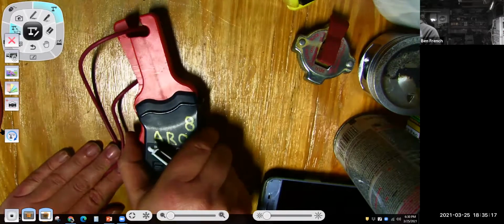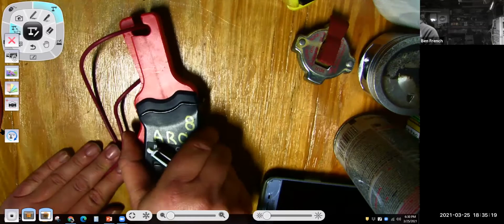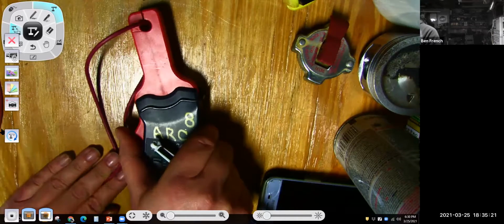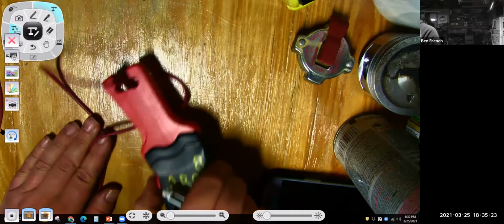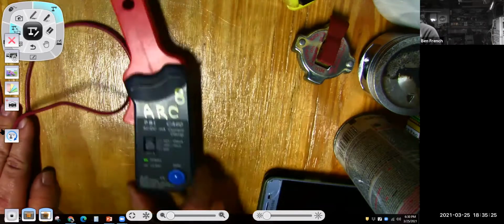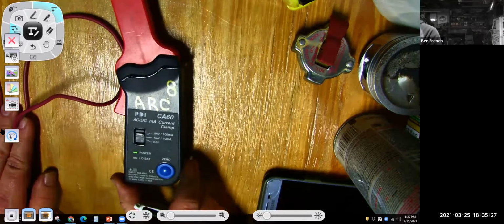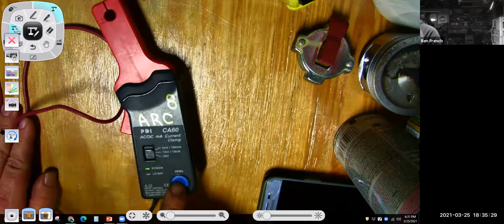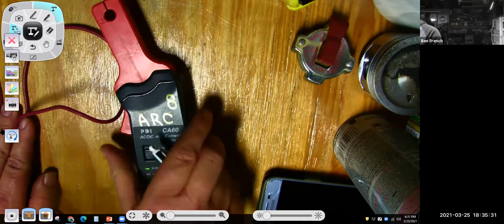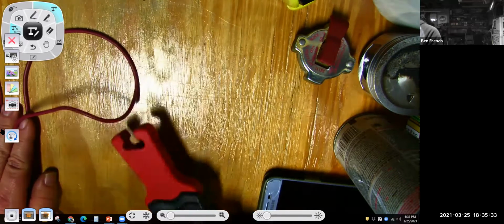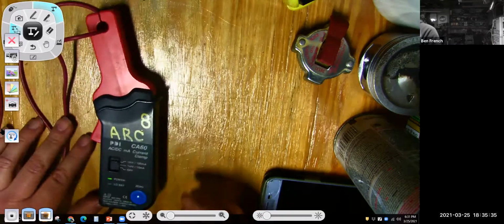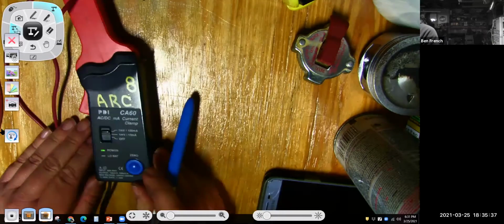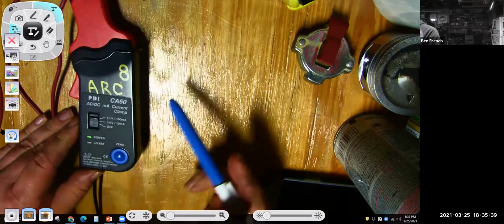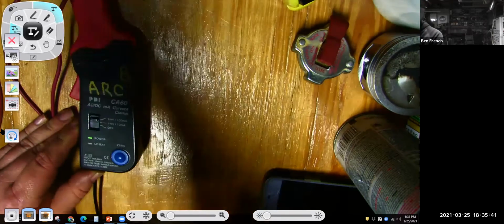Make sure it completely closes. If it's hanging open, it won't give a good reading. Before I clamp it around the wire, I need to hook it up to my meter and press the zero button. So I zero it out, clamp it around the wire, and then pay attention to what setting I have this thing on.